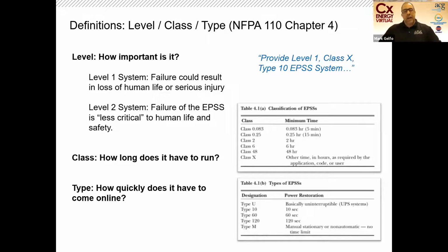The codes also define how long generators have to run and how quickly they have to come online—often within 10 seconds or maybe 60 seconds of the loss of power. We use terms like Level 1, Class 10, Type 10 system: Level 1 means it's the most important system, the class defines how long it has to run and how many hours of fuel you must provide, and the type defines how quickly it has to come online. All of that is defined by different parts of the code, with its own terminology.